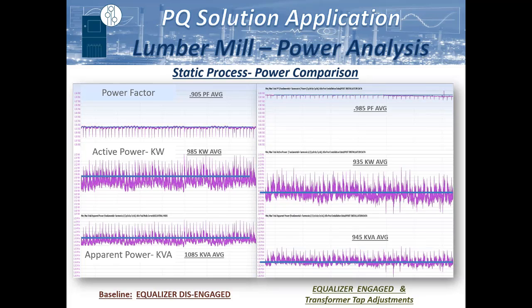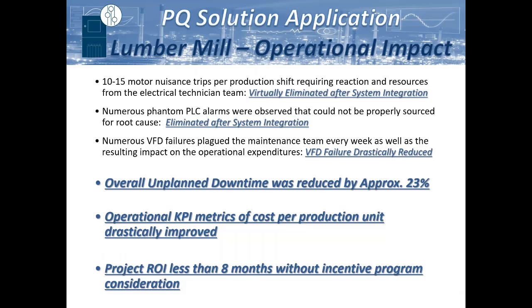You look at the active power going from 985 kilowatt average to a 935, and their apparent power going from 1085 to 945. So we're basically collapsing this power triangle and then keeping it at a steady state. But what was most impactful to the operation was actually the improvement to their overall operation. They had one electrician per shift whose primary purpose was to go around resetting breakers and resetting VFDs. So they'd have about 10 to 15 nuisance trips per shift.